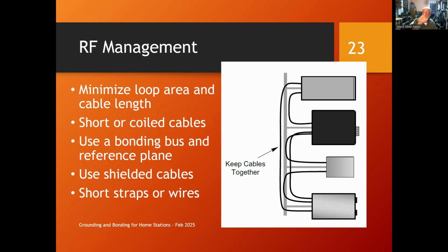And I was told that if you coil the cable up this way in a figure 8, the inductance of each half induces voltage that cancels, and so you wind up with a minimum amount of voltage. Otherwise, if you just coil it up, it acts like a sort of air core transformer to whatever it's picking up. So wind it up in a figure-8 shape, and you'll minimize the amount of voltage these things pick up.